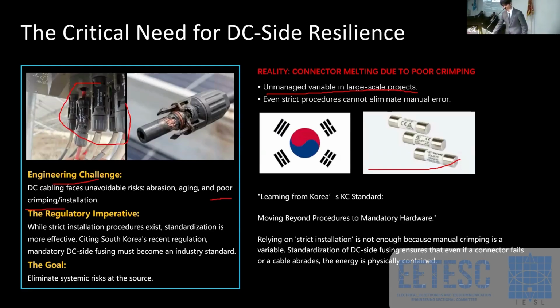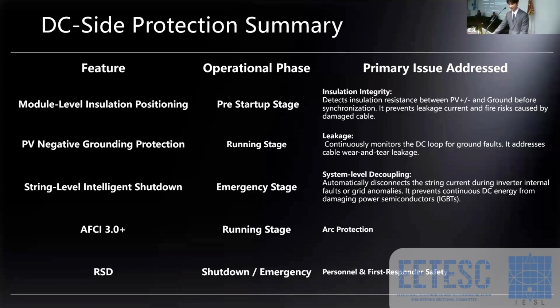So the last slide is about the DC side protection summary. From Sungrow, we have different phases, from the pre-start to the running stage to the emergency stage, even the shutdown stage. No worries about this, let me introduce them one by one. From the module-level insulation positioning, it's well known as the ISO check. At the very beginning of the start stage of the inverter, the inverter has not been connected to the grid. So the system will detect the insulation between the PV terminals and the ground, and it prevents current leakage and fire risks caused by damaged cable or poor connection.